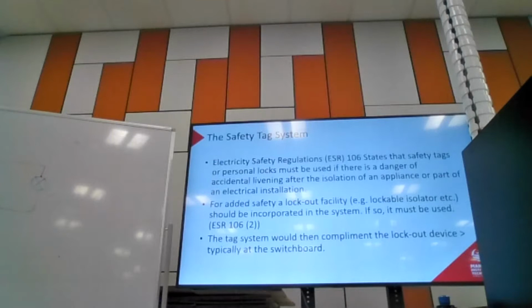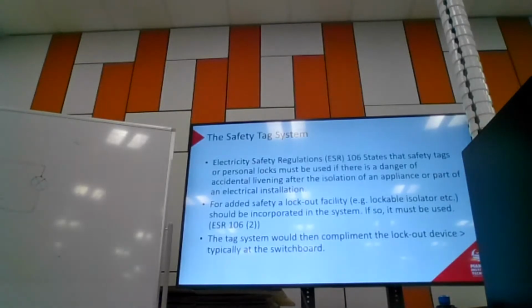So it says that a person carrying out works on works or installations that are isolated from a power supply must, if there is a risk of unintentional enlivening of the works or installation, ensure that suitable notices warning against enlivening are fixed at a point where the power supply may be connected or restored. So it doesn't say that we specifically have to use a danger sign, but it says a suitable notice.